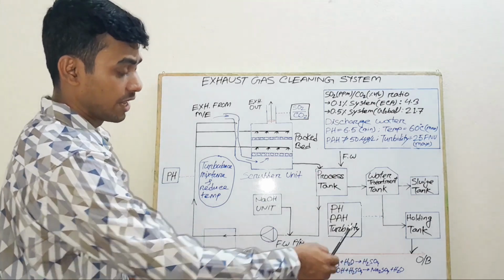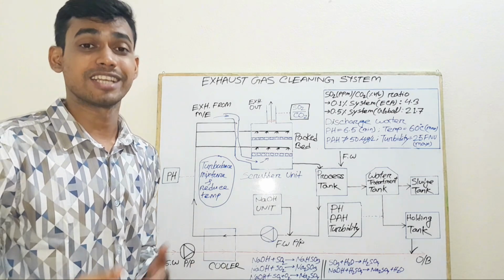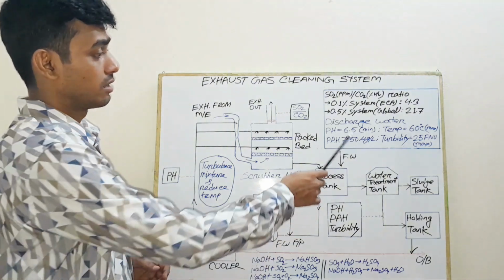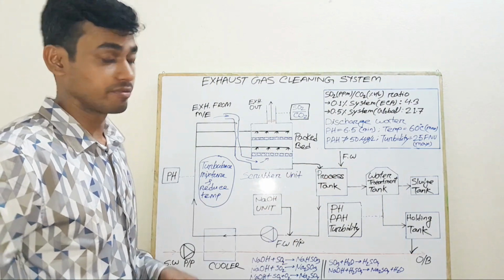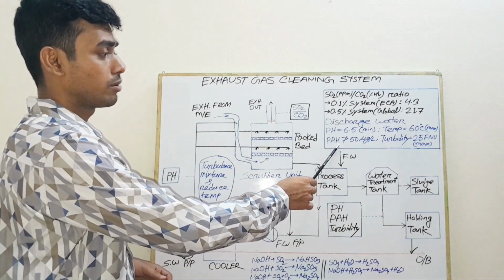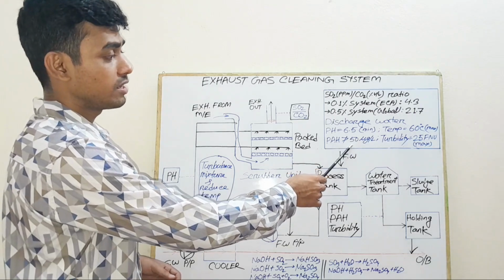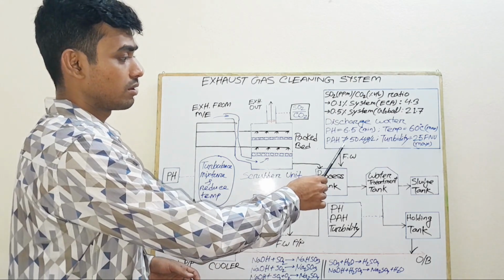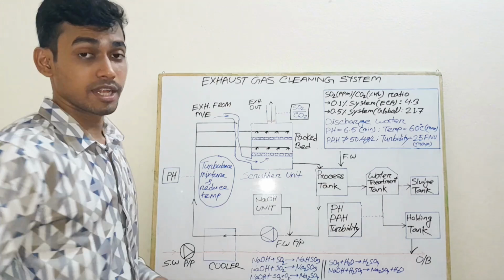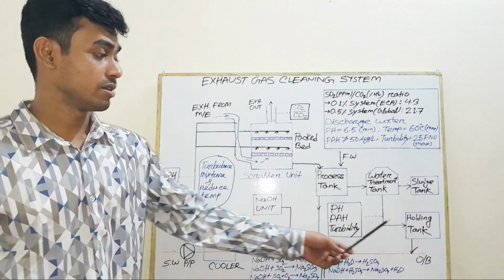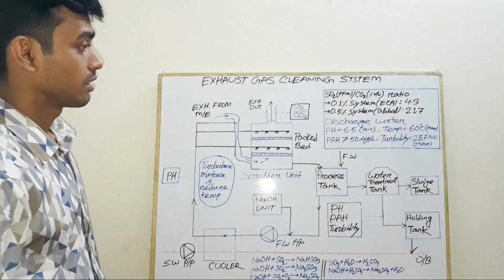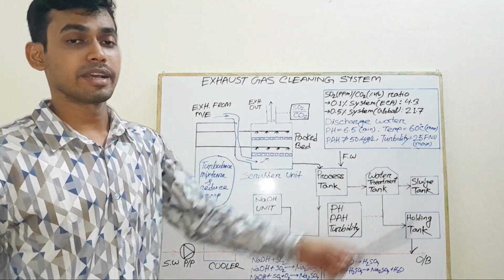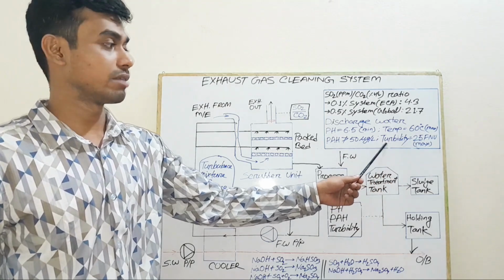If the pH is less than 6.5, that means it is acidic, but the discharged fresh water cannot be acidic. The polyaromatic hydrocarbon range is not greater than 50 microgram per liter. That means polyaromatic hydrocarbon particles must not be greater than 50 microgram per liter of discharged fresh water, and the turbidity is 25 FNU at maximum. FNU is the unit of turbidity.